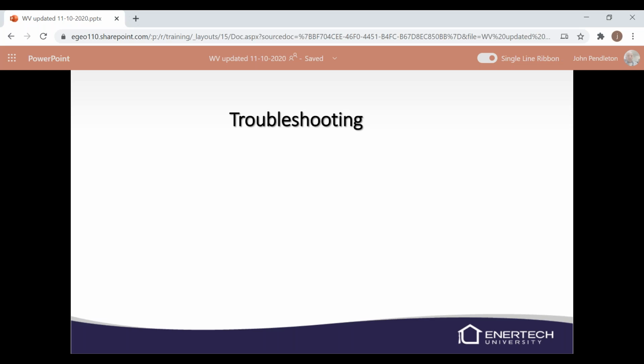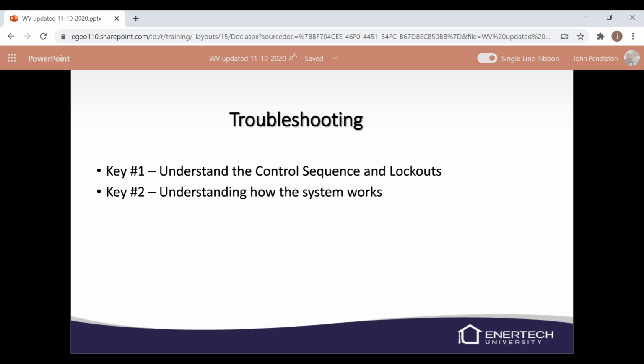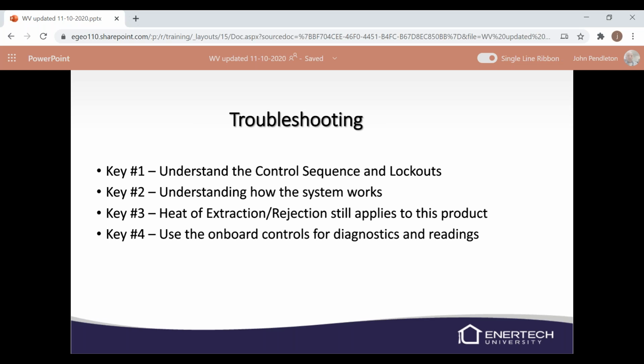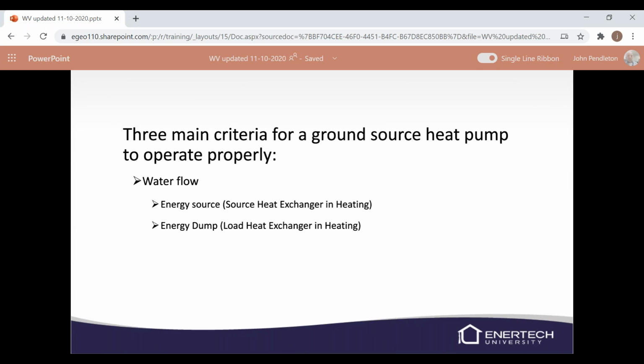We'll get into a little bit of troubleshooting, not as much today, but basically you've got to understand the sequence of operation, how the system works. Heat of extraction and heat of rejection still apply to this equipment. And we're going to use onboard controls for the diagnostics and readings, but we always want to back those up with trusted tools that we carry on our truck. We've got to have water flow. That's the biggest thing we have problems with this unit, is locking out on water flow. And it tends to be more on the load side than it does on the source.